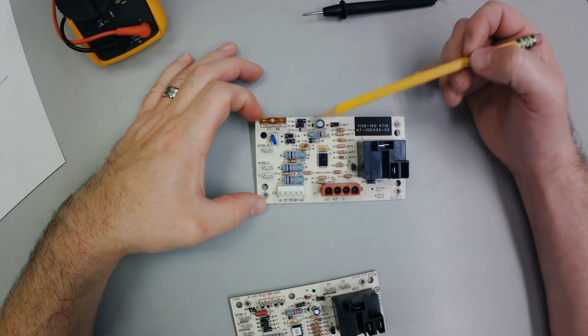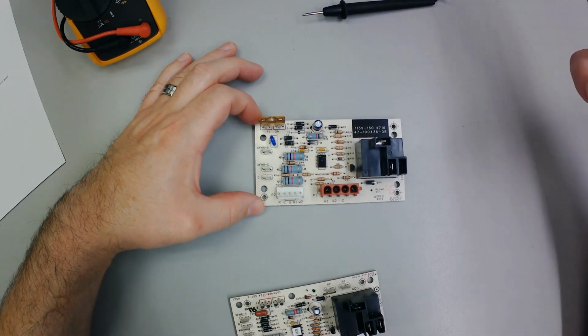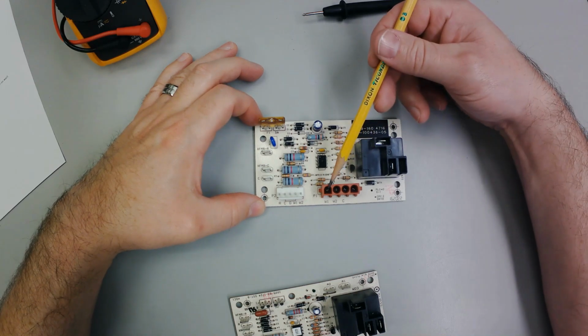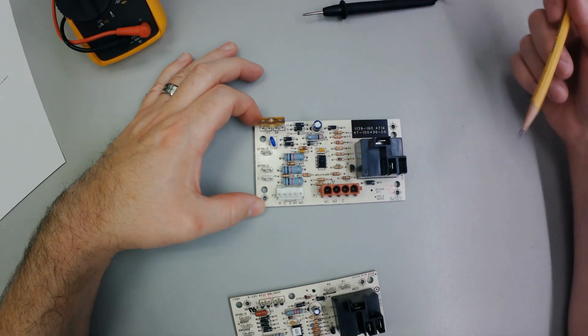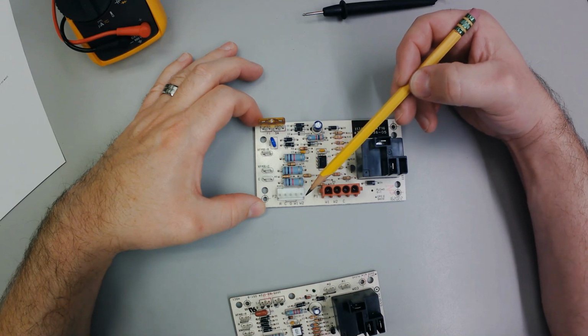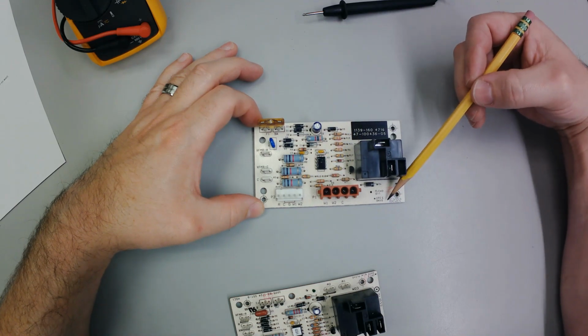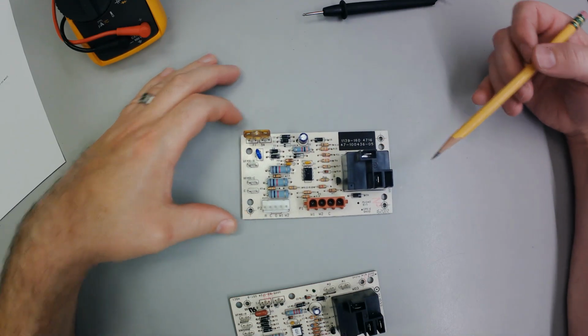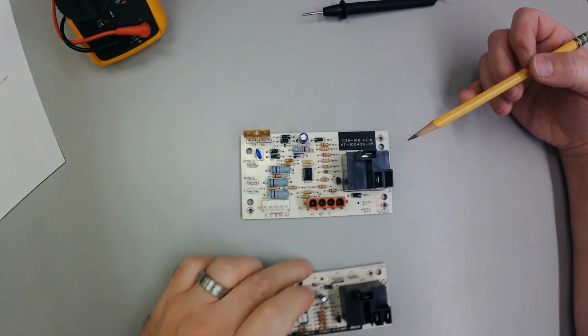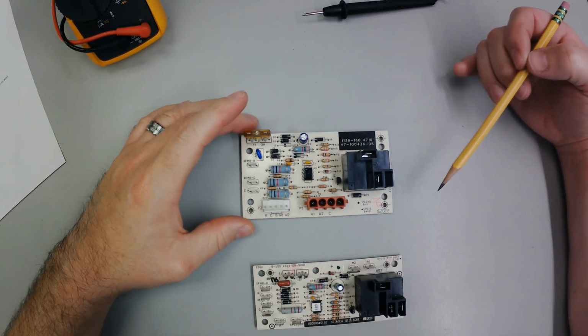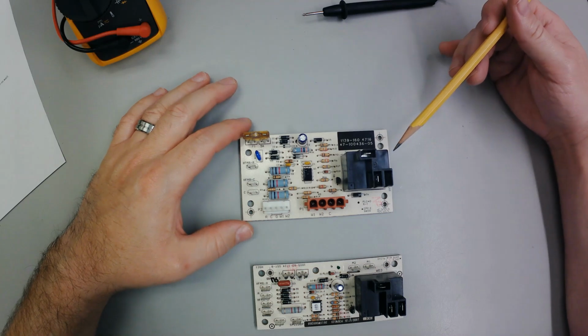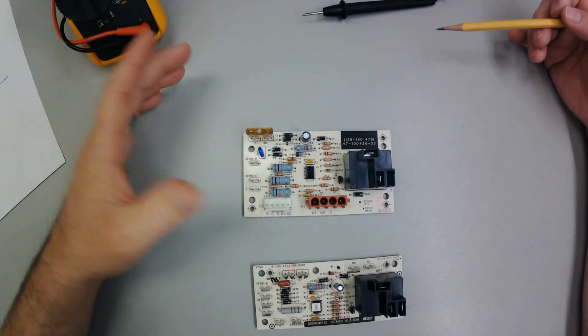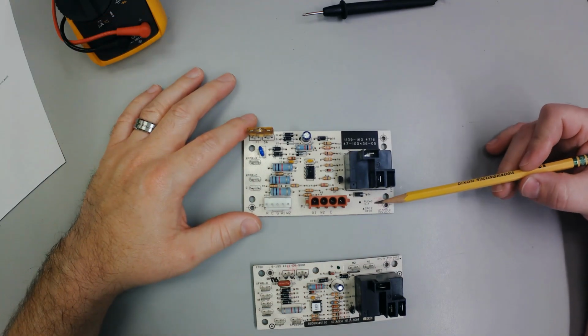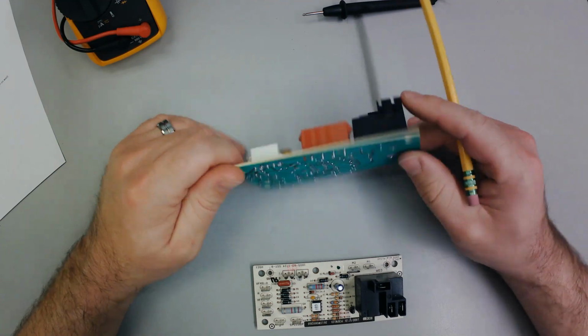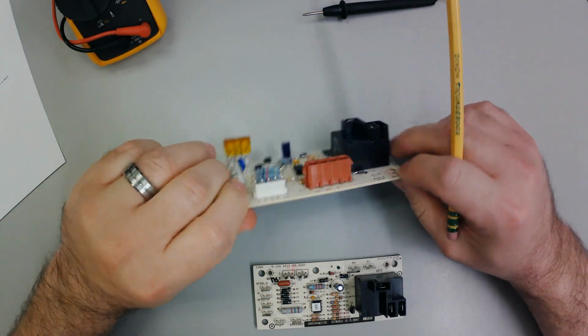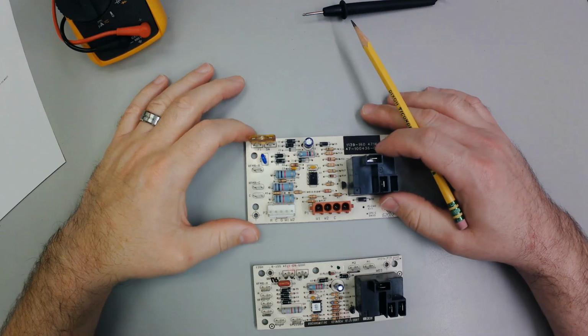So lots of similarities. Some of the biggest are this W and W2 or W1 and W2 connection. Why do I have that on the board? Why don't I have park terminals? Why do I have just one switch on this fan relay? That kind of goes together, the W and the fan relay stuff. The park terminals, I couldn't tell you. I wish they'd just solder in a couple dummy spots right here. Doesn't take up any room. You got plenty of space for it. And it would kind of dress it up a little bit.